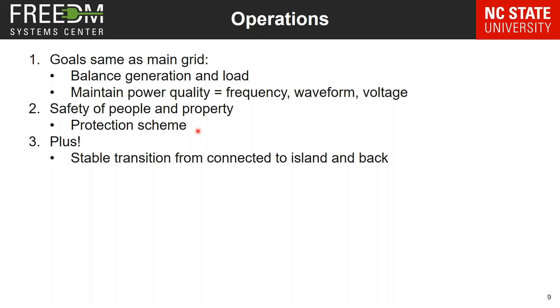But we're not done. You've also got to figure out how to operate your section of the grid when you isolate, or island, and then even when you transition back to being connected to the grid. There are several ways to do that. Some microgrids, when they detect a loss of power in the main grid, are designed to go dark, mainly for safety reasons, and then bring things back up after a momentary outage, enough to disconnect a transfer switch between the main grid and the microgrid. NC State can actually operate several of its campuses as a microgrid, but not with that seamless transition—they wait a period of time and then power some of the loads on campus.